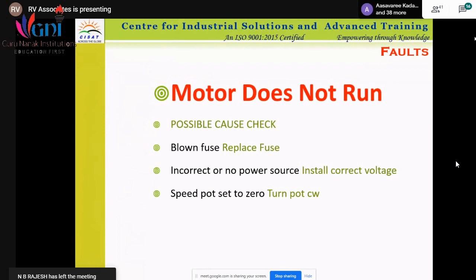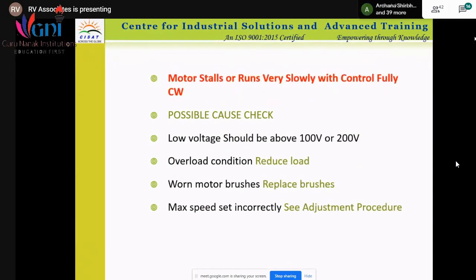So you have to enable the system, and the motor will start. But this is only in case of the drive, not for the normal motor. A normal motor will start whenever you give the supply. There is a contactor, and the contactor will act, or if there is a starter, the starter will act, and the motor will start, giving a heavy starting current.